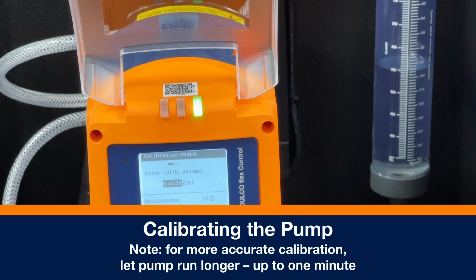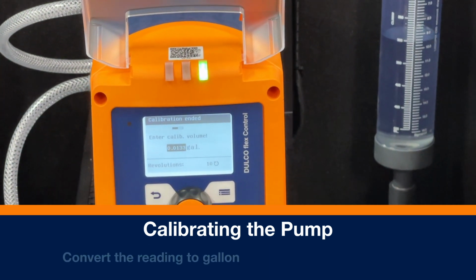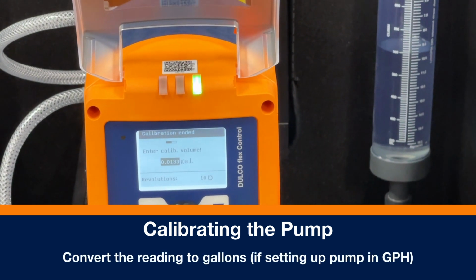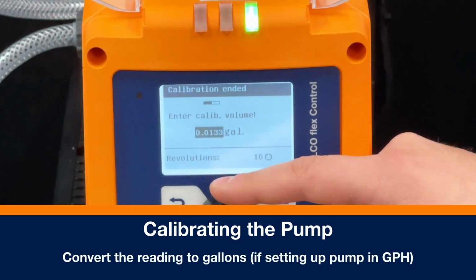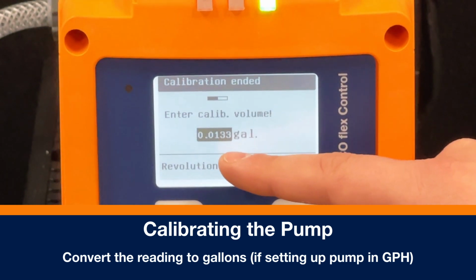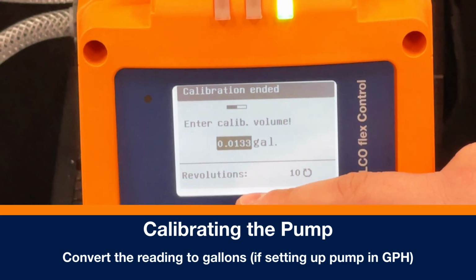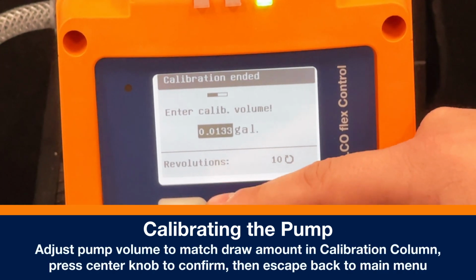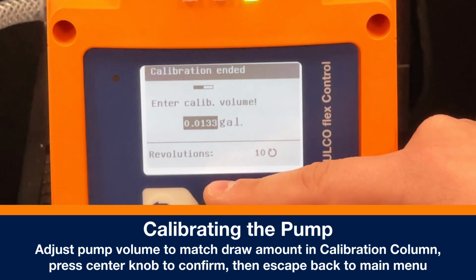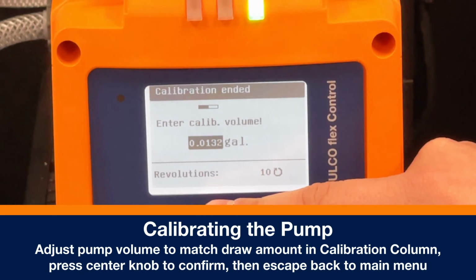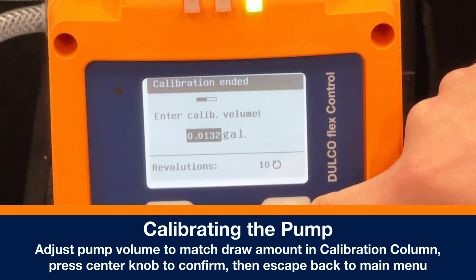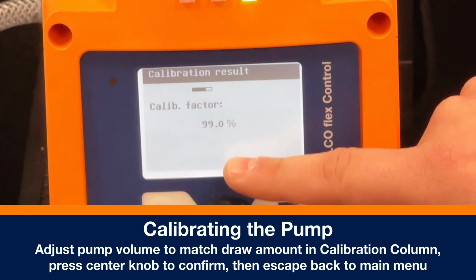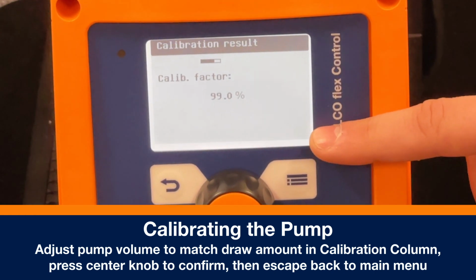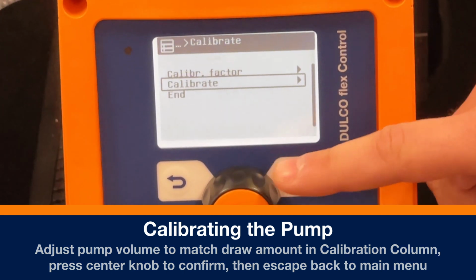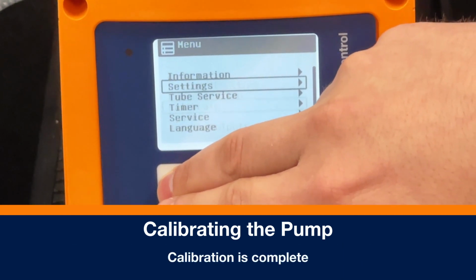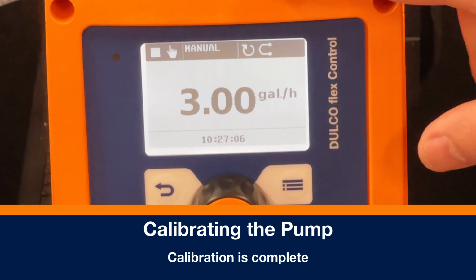After 50 milliliters, we will already know that 50 milliliters is 0.0132 gallons, which the pump sees as 0.0133. So I could say that calibration was pretty good, but I'm going to make it that 2. And I'm going to press OK. All right, and we have a calibration factor of 99%. Start now. Escape all the way back to the front, and then we're ready to start running this pump.